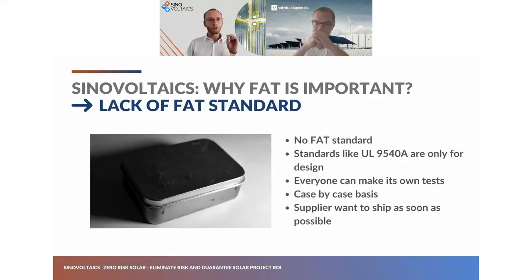Last but not least, why you should be really careful about FAT and really focus on it is that today there is no standard for FAT. If you have some experience with BSS, you may have heard about standards like UL 9540 and UL 9540A, but those are only specifically done for the design phase of a BSS. There won't be any tests for the manufacturing of your BSS. Meaning that for the FAT right now, it's a bit like the Far West. Everyone is making their own test.